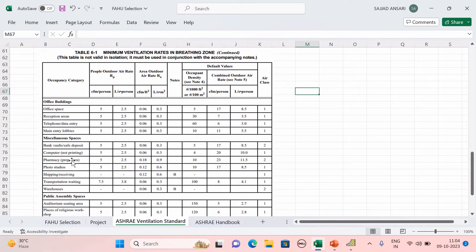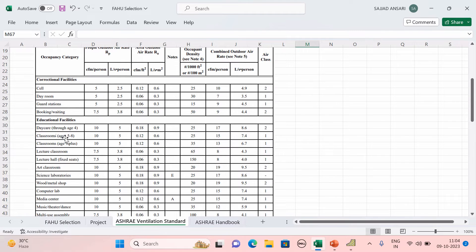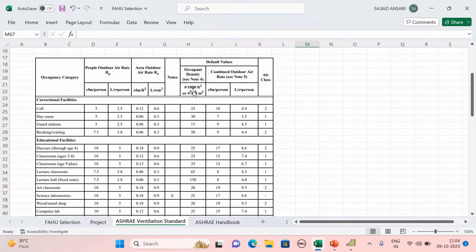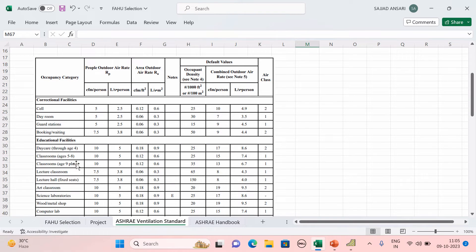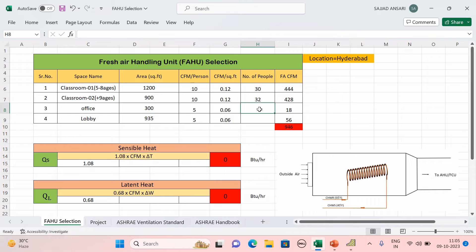For Classroom 1 (ages 5–8), the ASHRAE recommended occupant density is 25 people per 1000 square feet. Our classroom area is 1200 square feet, so by cross multiplication we get approximately 30 people. For Classroom 2 (ages 9+), the density is 35 per 1000 square feet; with 900 square feet area we get approximately 32 people.